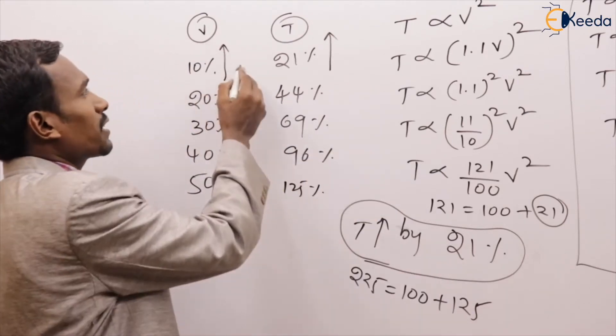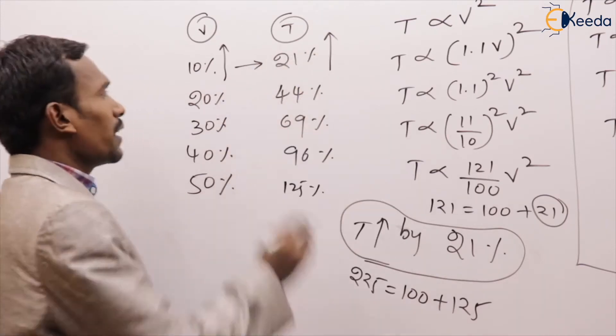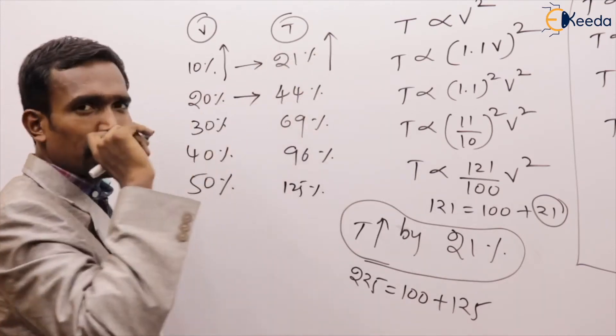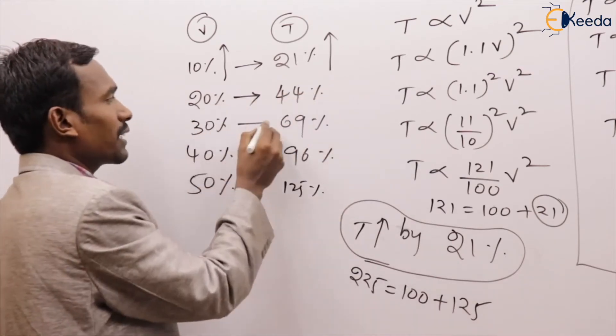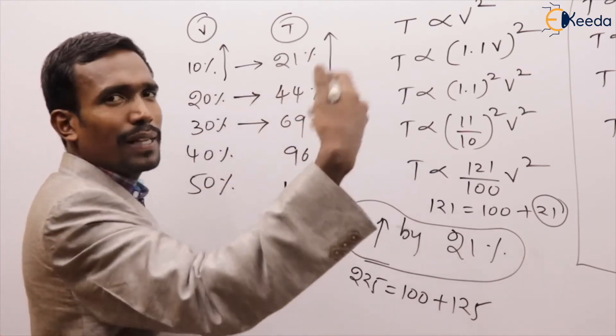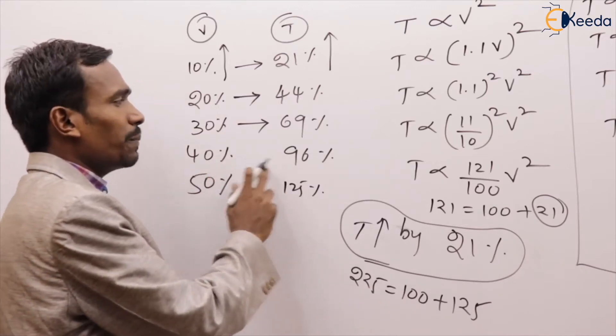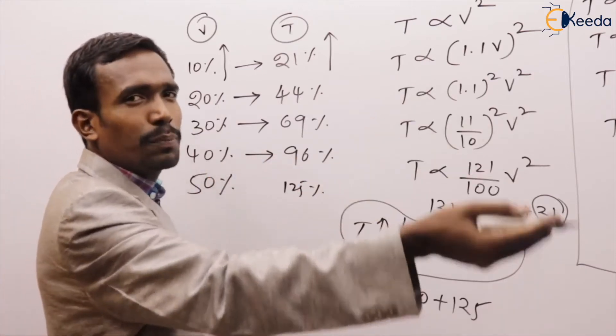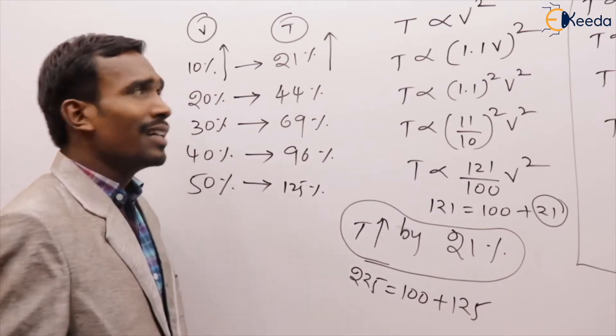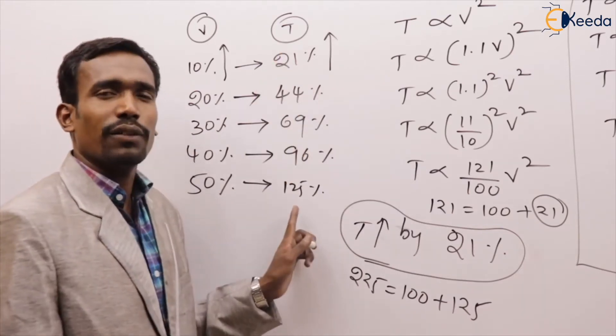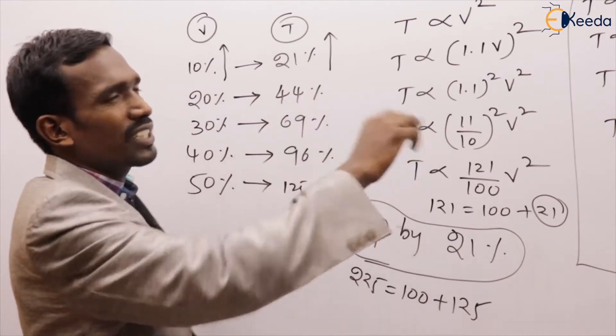Summary: if voltage increased by 10%, torque increased by 21%. By 20%, torque increased by 44%. By 30%, torque increased by 69%. By 40%, torque increased by 96%. By 50%, torque increased by 125%. This is for voltage increases.